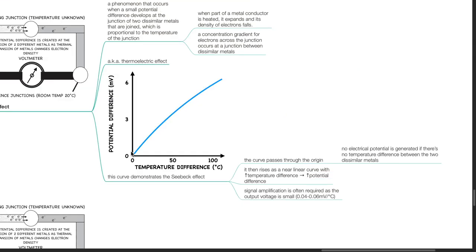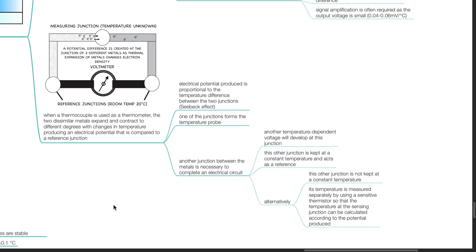This curve demonstrates the Seebeck effect with the x-axis referring to temperature difference and the y-axis measuring potential difference. The curve passes through the origin — no electrical potential is generated if there is no temperature difference between the two dissimilar metals. It then rises as a near-linear curve with increasing temperature difference resulting in increased potential difference. Signal amplification is often required as the output voltage is small: 0.04 to 0.06 millivolts per degree Celsius. The electrical potential produced is proportional to the temperature difference between the two junctions.